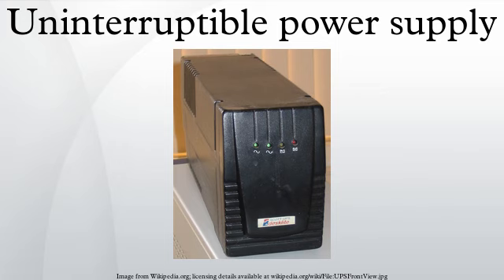Technologies. The three general categories of modern UPS systems are online, line interactive or standby. An online UPS uses a double conversion method of accepting AC input, rectifying to DC for passing through the rechargeable battery, then inverting back to 120 V/230 VAC for powering the protected equipment. A line interactive UPS maintains the inverter in line and redirects the battery's DC current path from the normal charging mode to supplying current when power is lost. In a standby system, the load is powered directly by the input power and the backup power circuitry is only invoked when the utility power fails. Most UPS below 1 kVA are of the line interactive or standby variety, which are usually less expensive.